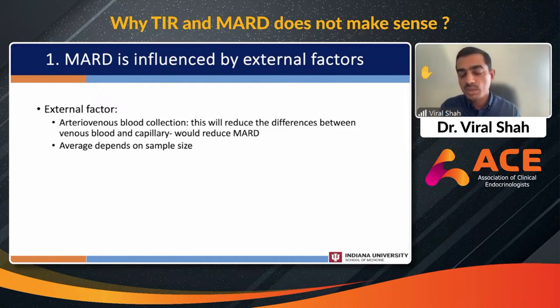real environment, where you are out in the field. That's why the MARD doesn't make sense in a real situation. It's slightly, as Mithun said earlier, a manipulated number. And also, it's an average, it's a mean—the first letter of MARD is M. M stands for mean. So it depends on the sample size. If you have a large sample size, it would be much better for MARD than a smaller sample size.